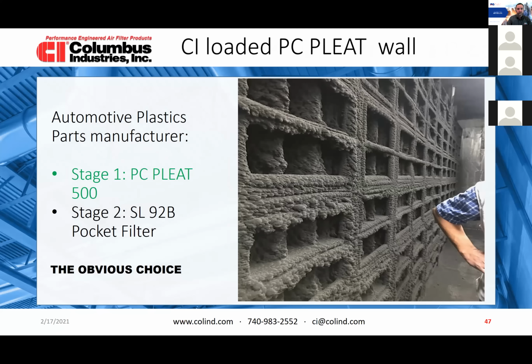This is the front of the filter, and you can see how from here all the way to the end, the booth is evenly loaded. In this booth, we actually tried to do the hotspot, but in the end it was not possible because, I'm not joking, all the boxes were within 2 pounds. That's how air was flowing through that booth. It was fantastic. Anywhere you look in the booth, it's movement.